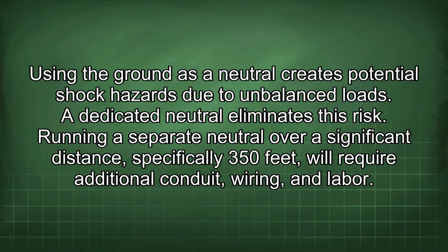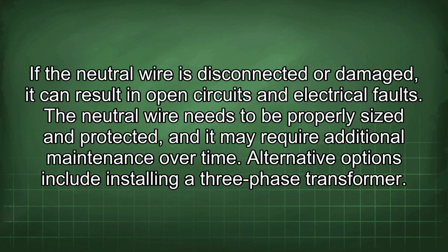Running a separate neutral over a significant distance, specifically 350 feet, will require additional conduit, wiring and labor. If the neutral wire is disconnected or damaged, it can result in open circuits and electrical faults. The neutral wire needs to be properly sized and protected, and it may require additional maintenance over time.